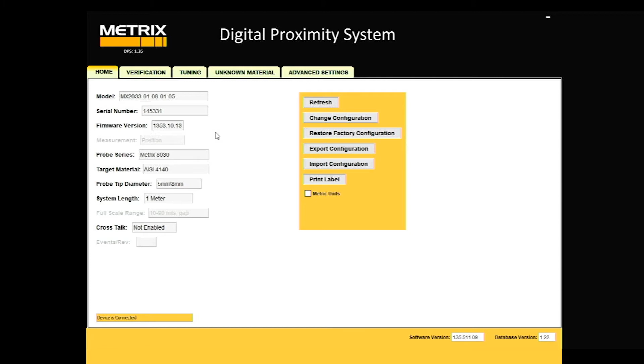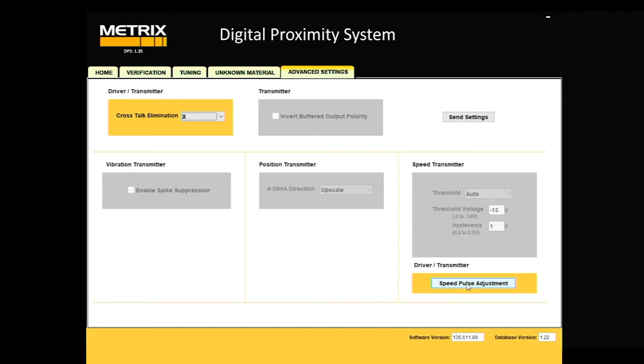So to do that, we use the Digital Proximity System software. We connect to it via the USB connection at the bottom. You take off the DIN rail mounting, and you'll be able to connect to it. Then you go to the Advanced Settings tab. In the Advanced Settings tab, we have quite a few features. One is crosstalk elimination, but another is the speed pulse adjustment, and that's what we're going to use right now. I'm going to go ahead and adjust the pulse.